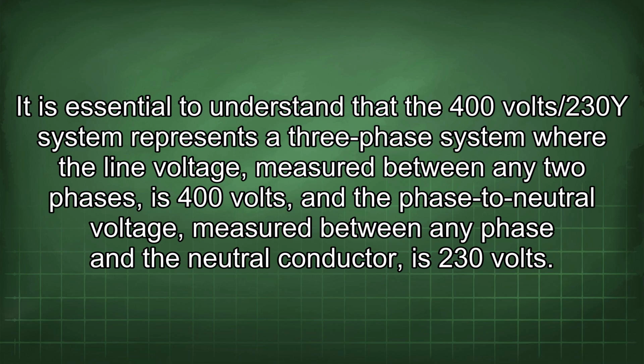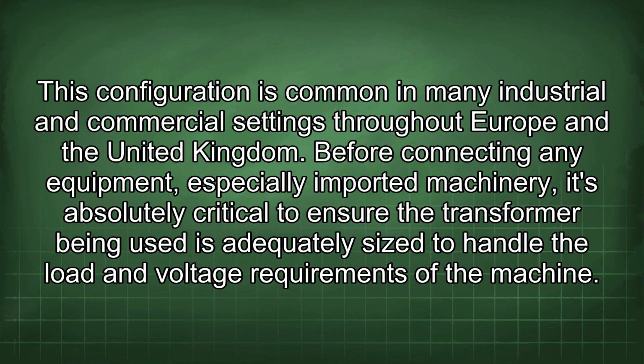It is essential to understand that the 400V/230Y system represents a three-phase system where the line voltage, measured between any two phases, is 400V, and the phase-to-neutral voltage, measured between any phase and the neutral conductor, is 230V. This configuration is common in many industrial and commercial settings throughout Europe and the United Kingdom.